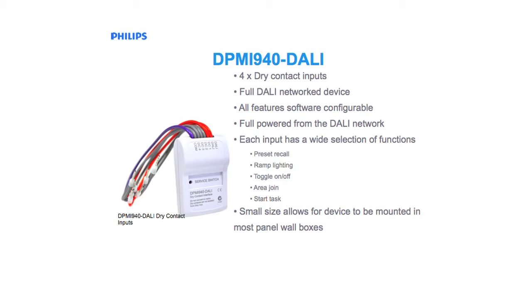Each of the dry contact inputs has an option of functions from preset recall, ramping, toggling on and off, or to start a task. The device is traditionally seen in a wall panel application picking up bell presses or button presses. From these button presses, it's able to perform any one of these functions. Instructions sent from this device can be used to affect lighting in its own DALI universe, multiple DALI universes or other Philips Dynalite load controllers.